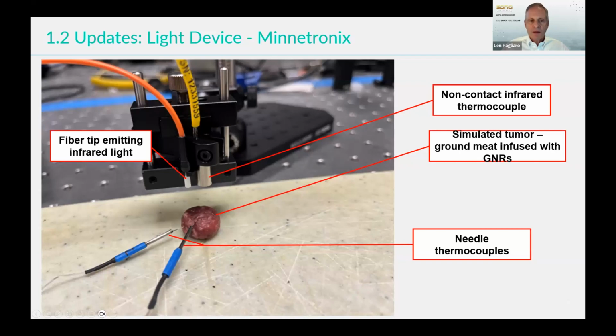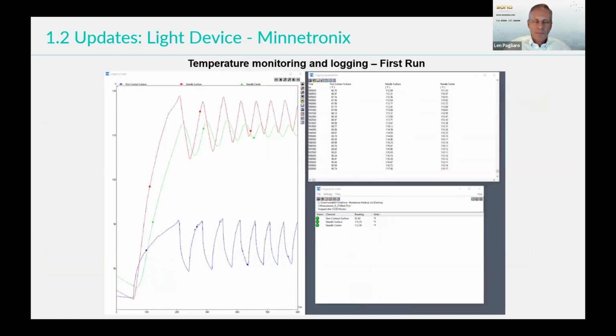One of the things we've got to do is make sure the calibration of the non-contact sensor is right, so we can monitor tumor temperature at multiple depths and under multiple conditions, and ensure we're getting accurate readings through the non-contact device.